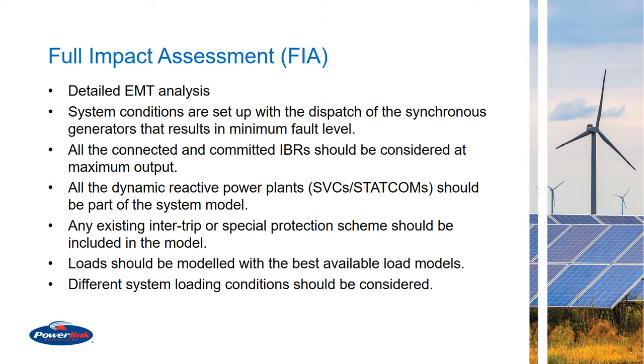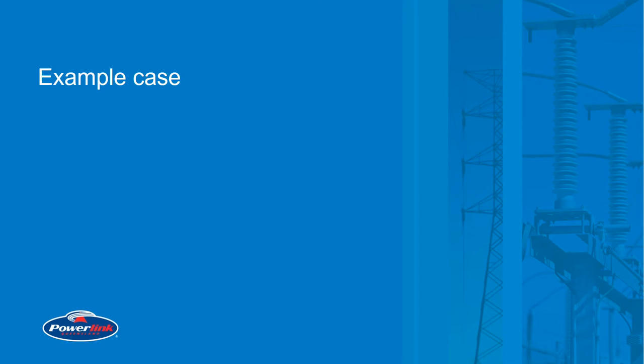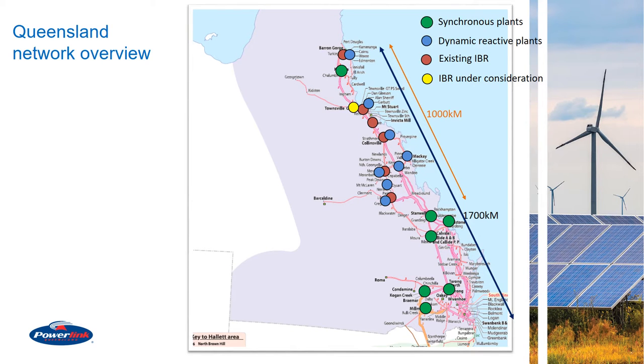If there are any inter-trip schemes or special protection schemes, those must also be included. Different loading conditions must be considered, and the best available load models must be used as part of this analysis. Next, I will be presenting an example case of an IBR that went through the FIA process.